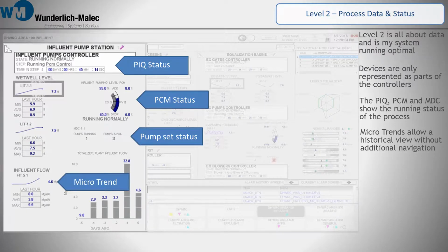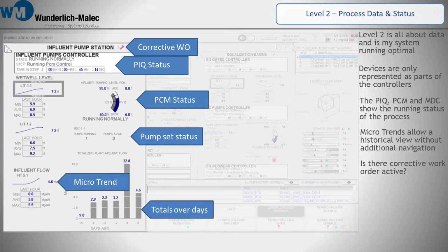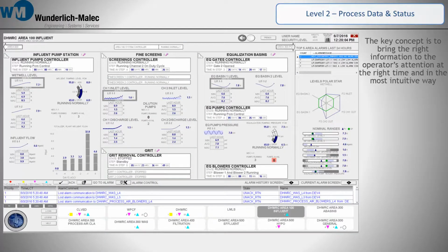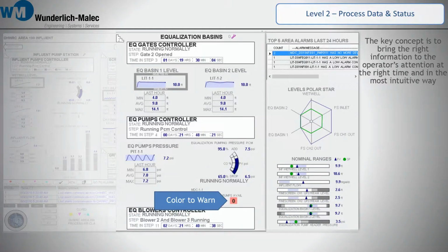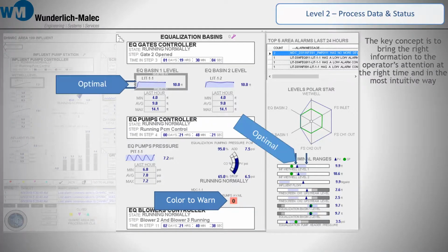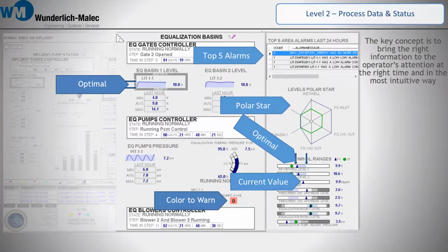Microtrends show a historical view without additional navigation, as well as the totals over the past 5 days. The wrench up top shows whether or not there's an active work order in the area. The key concept is to bring the right information to the operator's attention at the right time and in the most intuitive way, such as color to warn if no pumps are available, or if the process is in the optimal range. The current value and its relationship to the set point and alarming limits. A polar star showing the current condition of the area's performance and the top 5 alarms. At every level, situational awareness focuses on the most important data without having to open additional windows.